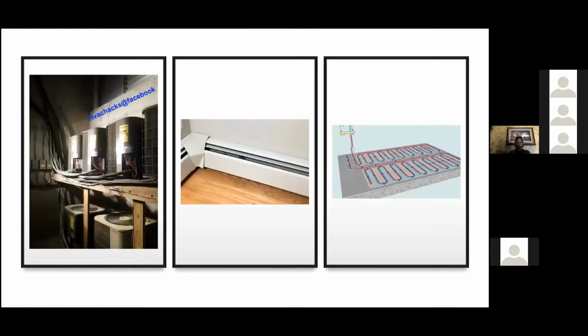some workarounds that folks have used. I remember when Daikin first came to the United States with VRF, and there was a lot of trim heat around because those VRF units, Ron has a background with Daikin, couldn't keep up when it got to be about minus 4. So then you'd have a lot of baseboard heat. Other alternatives, I've heard about people putting their outdoor units in their garage and keeping their garages warm. We're not going to be looking at that kind of a fix. We used to put the VRF outdoor units in little garages with doors that open and close. You can have a little boiler in your basement, that kind of thing.